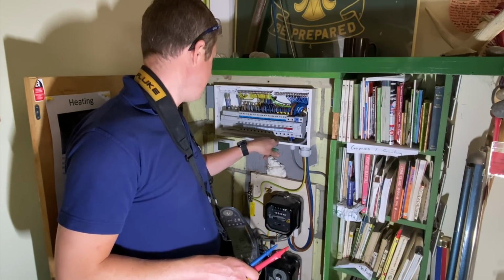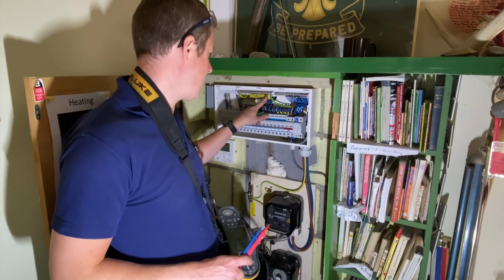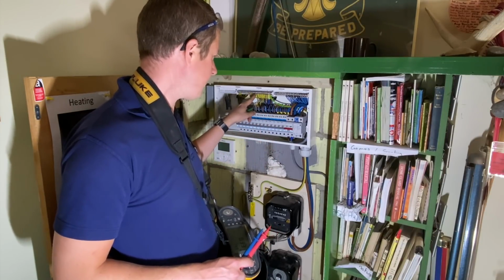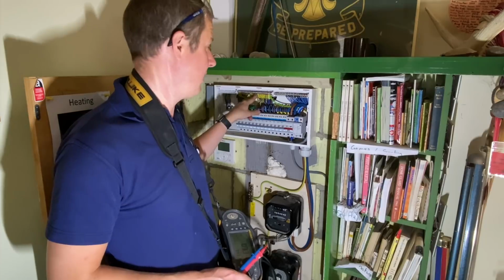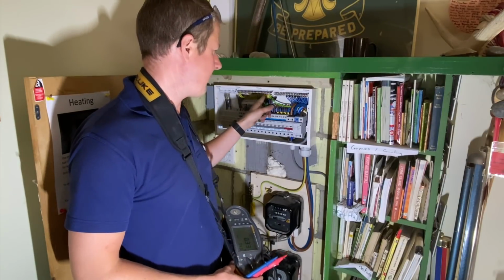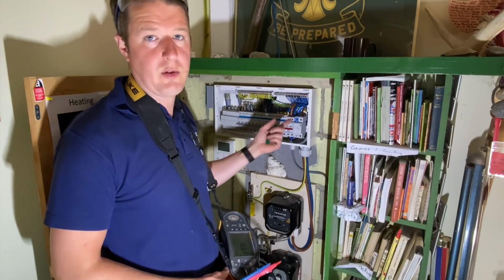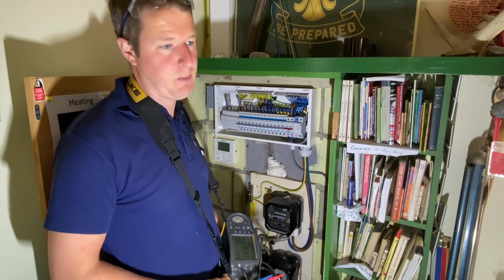our external earth fault loop impedance tests, and our Zdb tests done. So now what we have to do is test earth continuity, or continuity of CPCs, we call it, circuit protective conductors. We have to do those tests to make sure that all the final circuits have an earth at the various points.